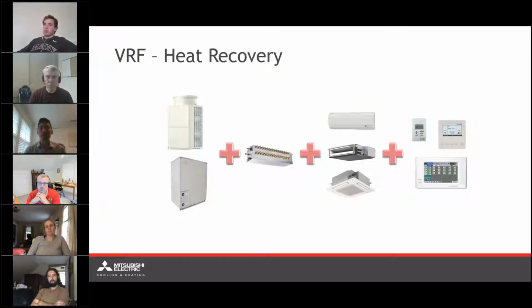Now, building off of this, the first topic we're going to be talking about today is our HEX unit fan coils, or heat exchanger units. These are our refrigerant-to-water heat exchangers. Ultimately, the VRF system itself is going to see these HEX units as just another fan coil on the system. So to the VRF system, it's the same thing as a wall-mounted unit, same thing as a cassette. It's just its own individual fan coil.